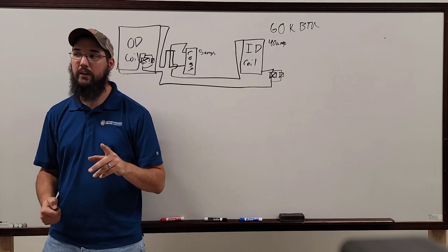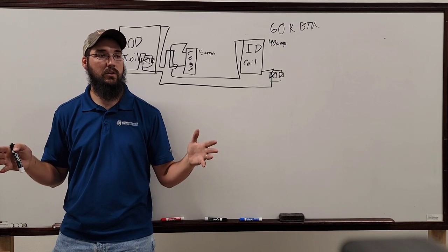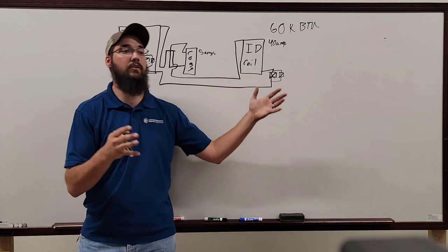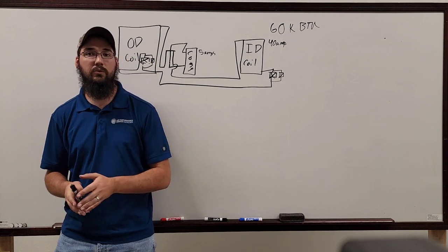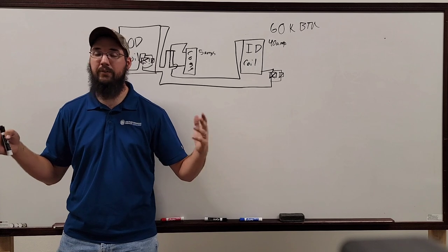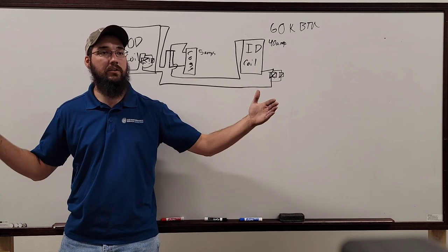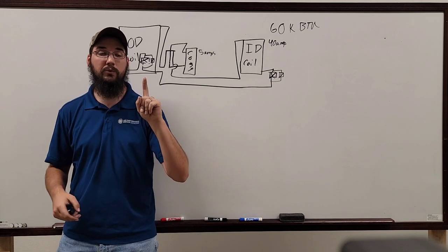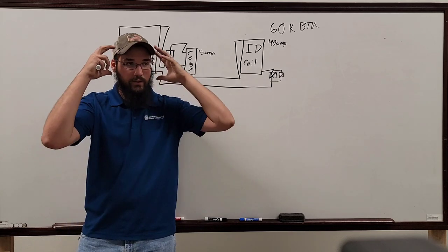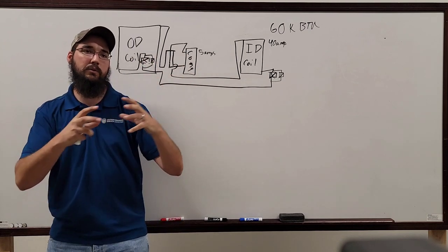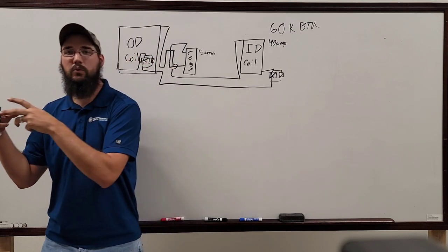But the point of that system is you're trying to reduce the number of cycles. An electric heater might cycle every 15 to 30 minutes. Well, that heat pump, if set up properly, if the airflow is proper, everything is done right, may literally run 8 hours and never cycle, but it keeps the house at proper temperature. So it's a design concept change between gas and electric heat and what we're trying to do on heat pump.